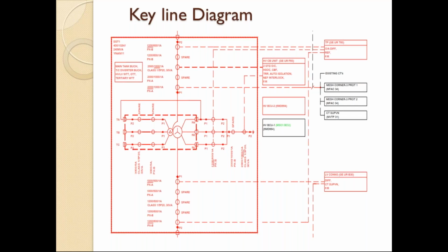So each CT has a different representation. In this figure, this is the auto transformer. Above it there are 5 CTs connected: 1, 2, 3, 4, 5. This first CT will always protect in this direction. If there is a circuit breaker, it will be located above the CT.